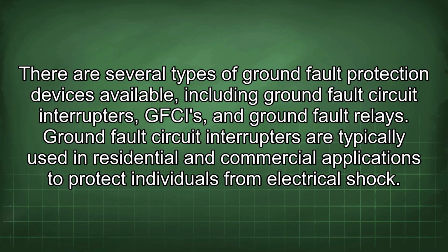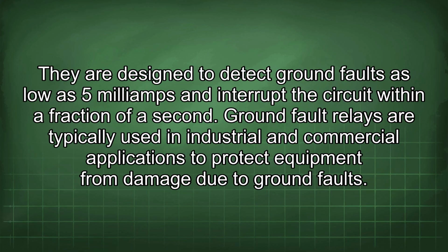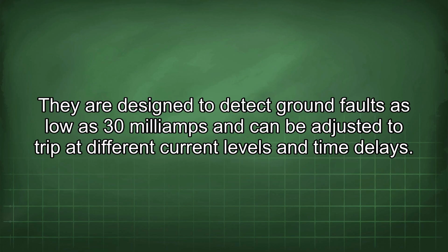Ground fault circuit interrupters are typically used in residential and commercial applications to protect individuals from electrical shock. They are designed to detect ground faults as low as 5 mA and interrupt the circuit within a fraction of a second. Ground fault relays are typically used in industrial and commercial applications to protect equipment from damage due to ground faults. They are designed to detect ground faults as low as 30 mA and can be adjusted to trip at different current levels and time delays.